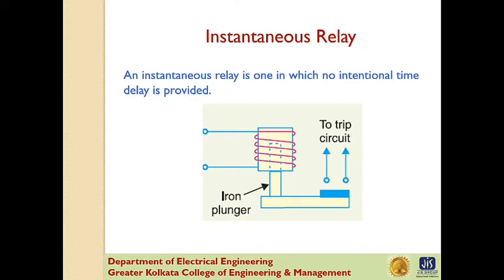Next, I will discuss relay timing. An important characteristic of a relay is its time of operation. By the time of operation is meant the length of time from the instant when the actuating element is energized to the instant when the relay contacts are closed. Sometimes it is desirable and necessary to control the operating time of a relay. For this purpose, mechanical accessories are used with relays.